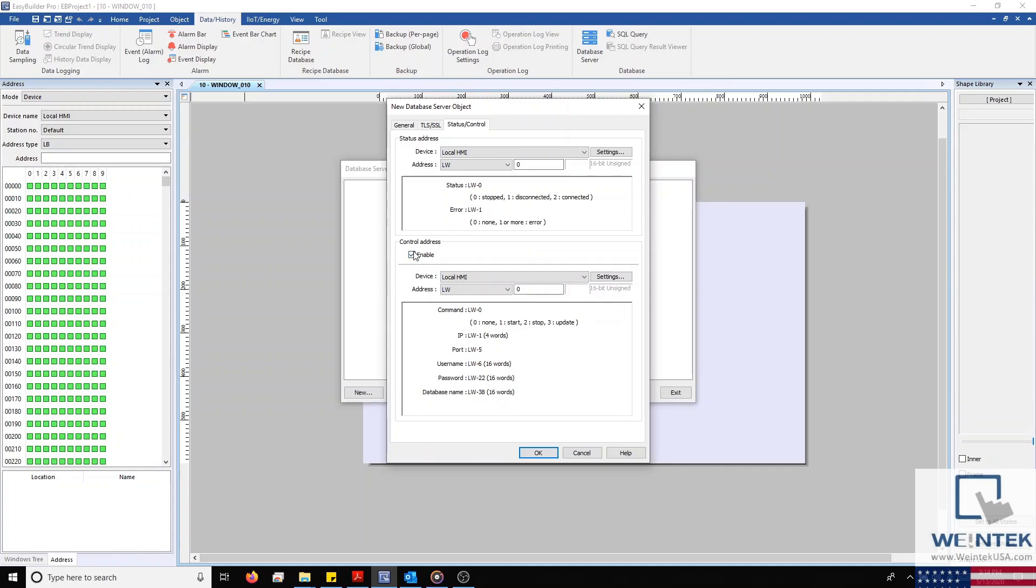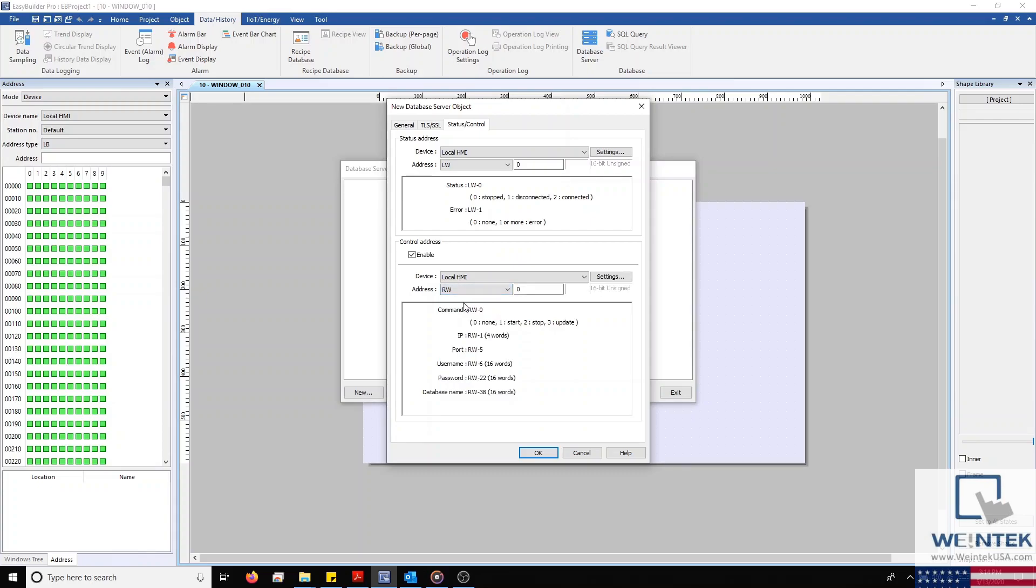Establishing a control address will allow us to edit our database server settings in case we need to make changes after our project has already been downloaded to our HMI. For this address, I'm going to assign it to our RW registry, which is our retentive registers. In doing so, any information entered will be saved in the event of a reboot or power failure.